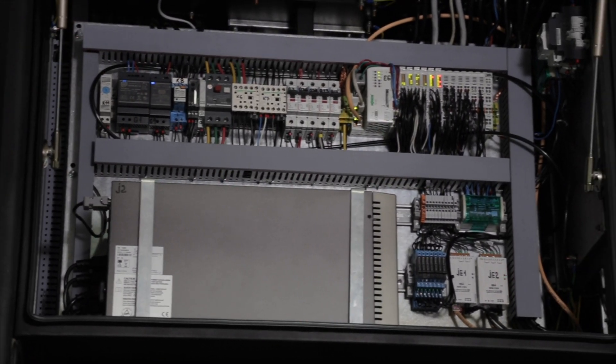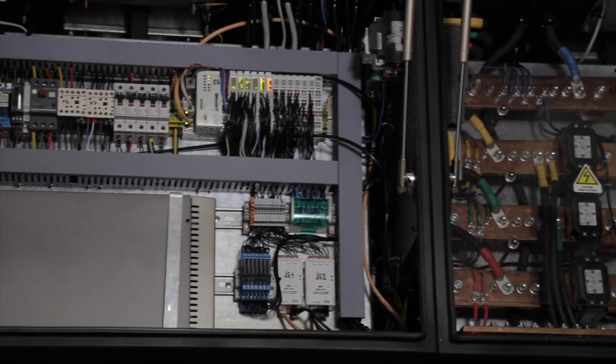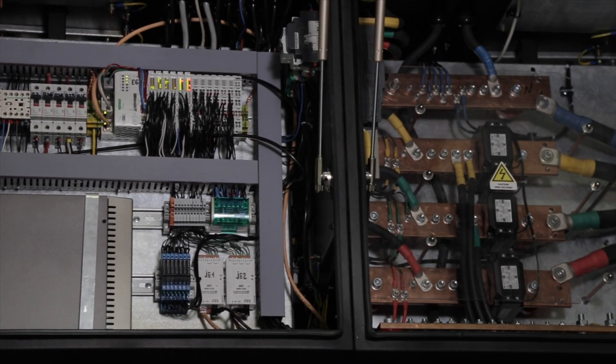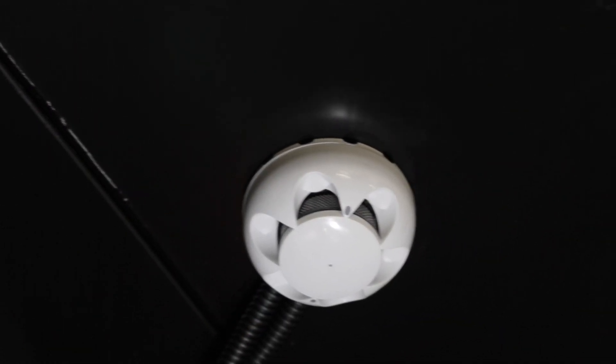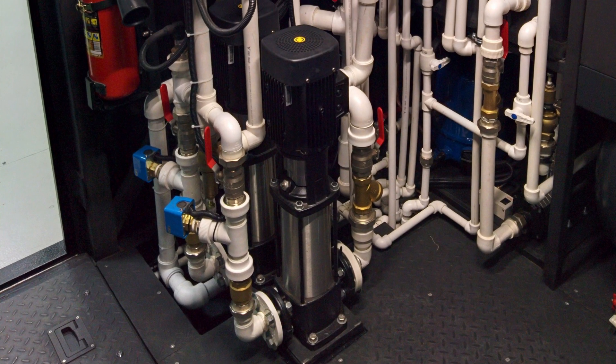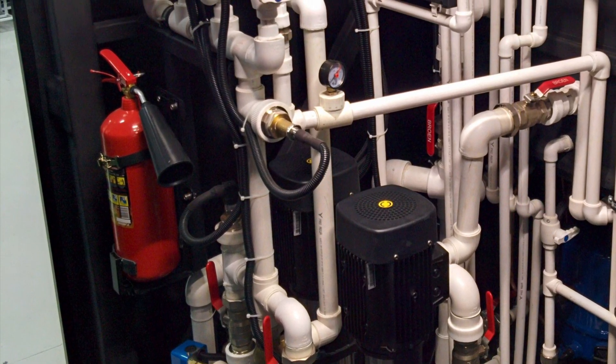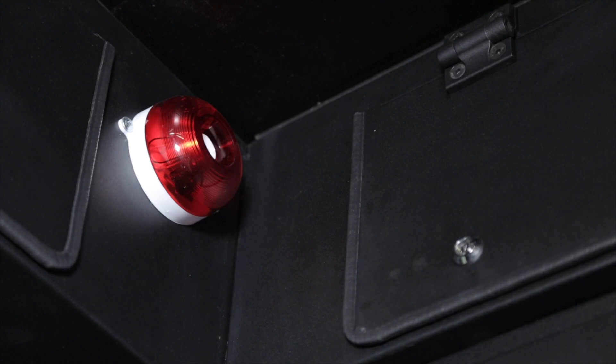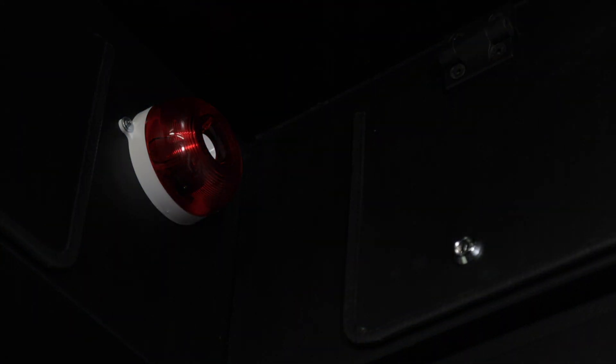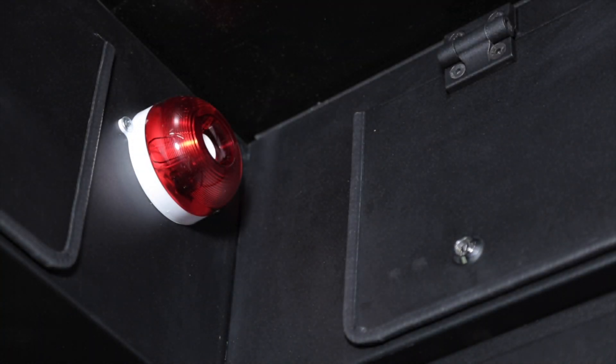All electric cabinets and cable ducts are airtight, have sealing on their doors and airproof inlets and outlets, which allows using an automatic firefighting system in each cabinet and the cable ducts. A safety gas-based firefighting system is used in the container. A fire alarm system and primary firefighting means are also provided in the module.